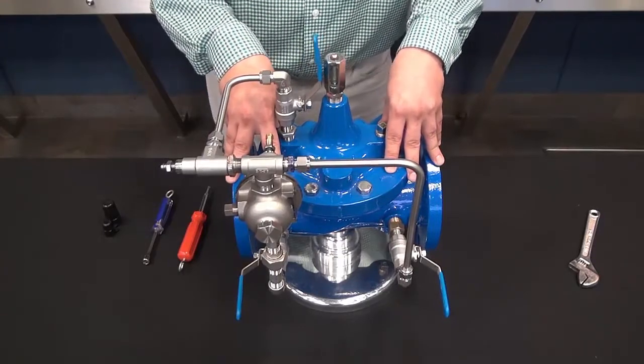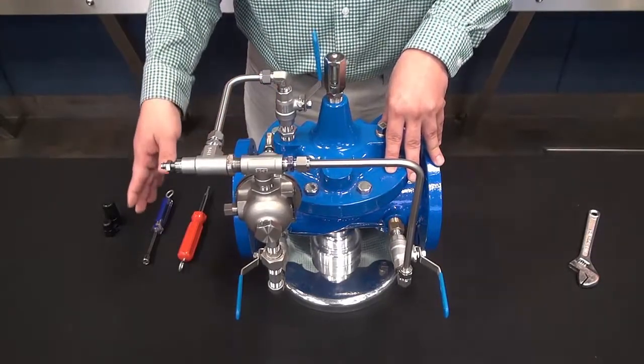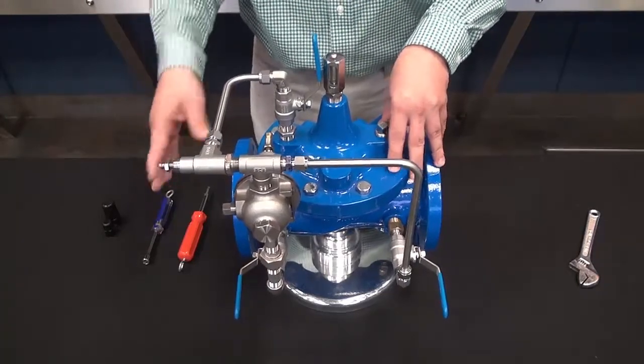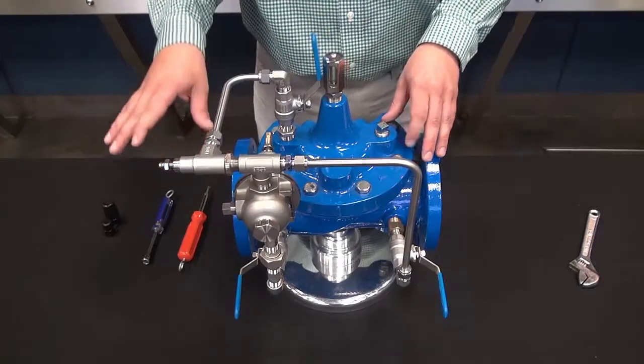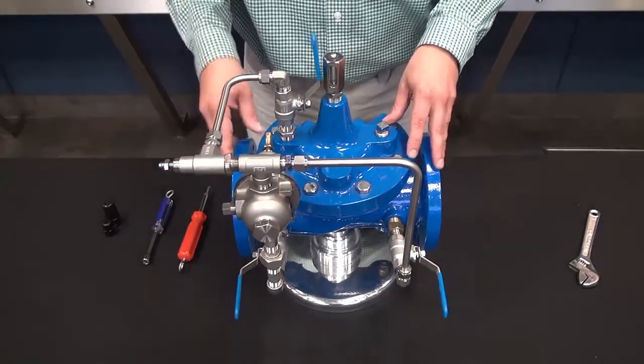Now a 90-01 pressure reducing valve is designed to maintain a downstream pressure regardless of flow rate, regardless of demand. It's always trying to find or modulate into the setting of the CRD.